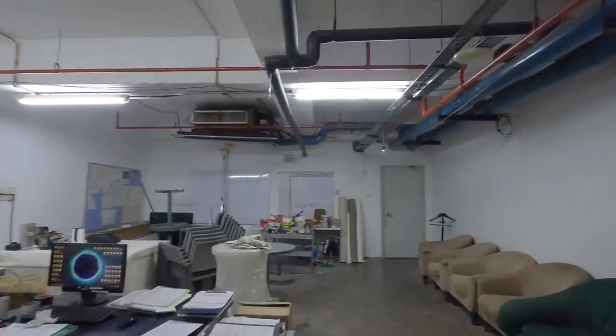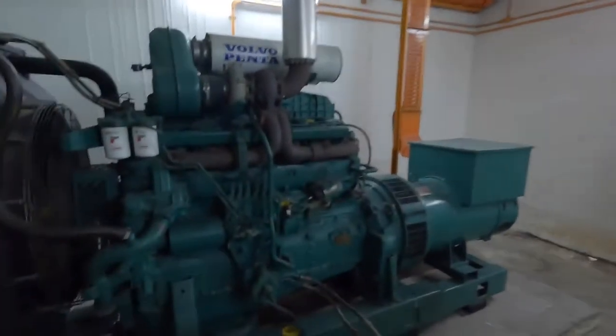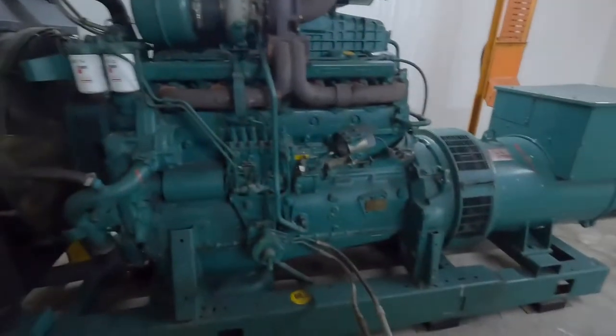All the hands-on tools are available. This is the AC Hotel Puantan Genset room. We have a Volvo Penta engine here. Before we test run the Genset, let's check the parameters first. Pump here a few times to avoid airlock. Let's check the fuel hoses — make sure there are no fuel leakages, no oil leakages, no engine oil leakages, and no radiator water leakages.